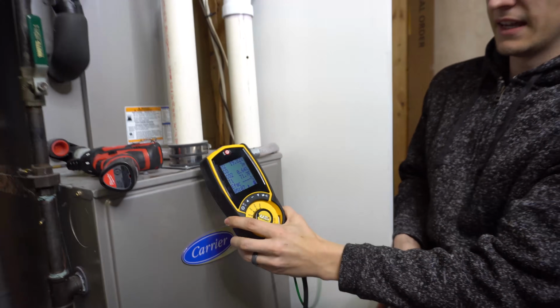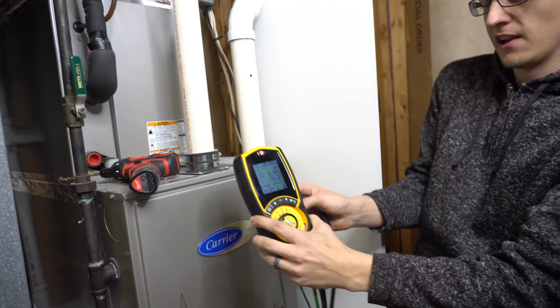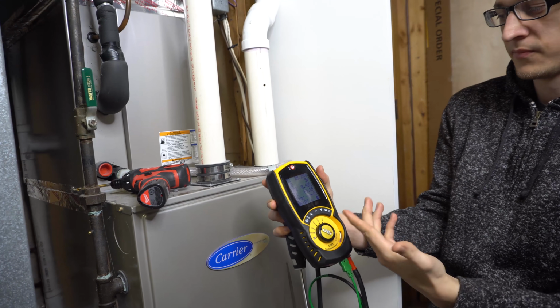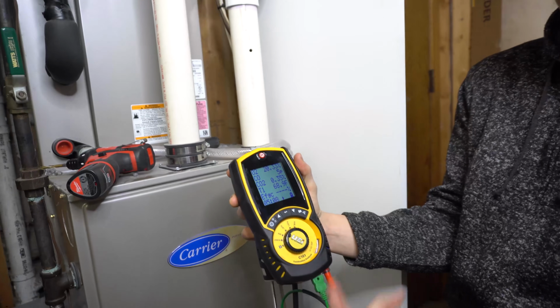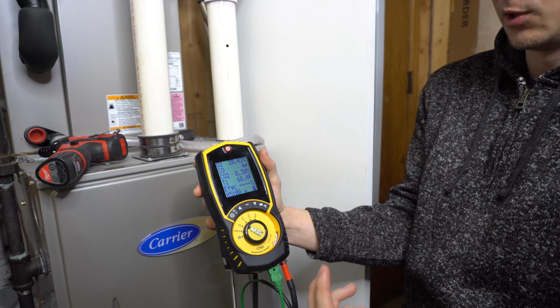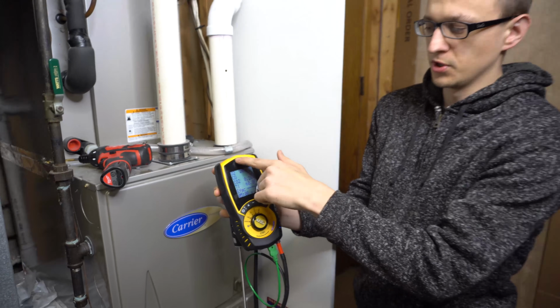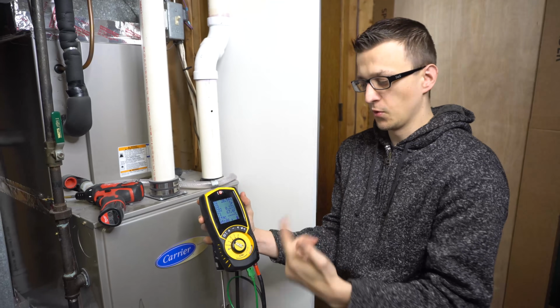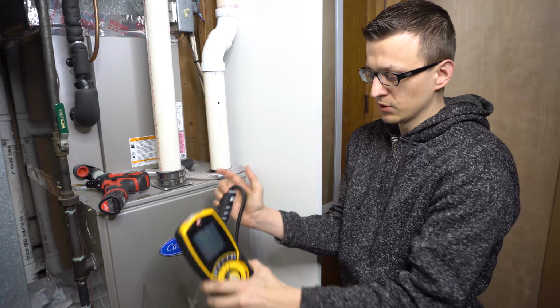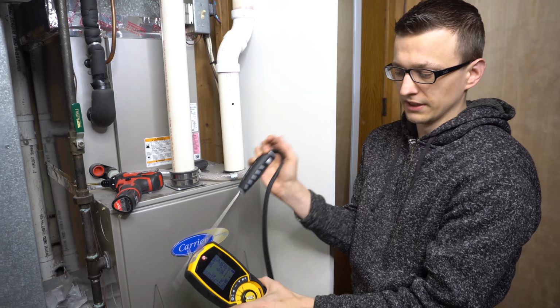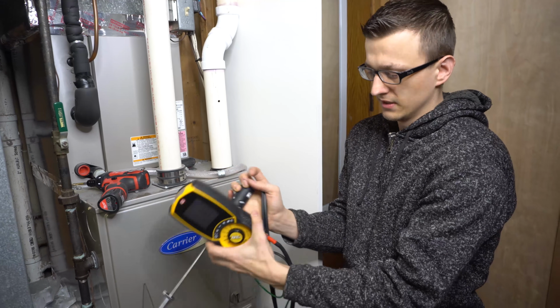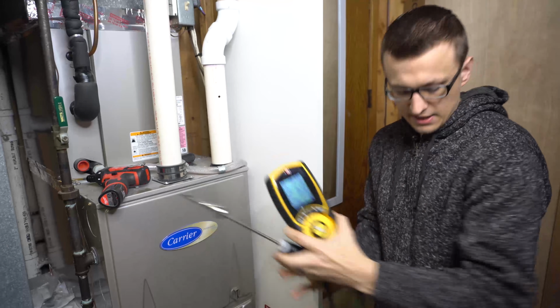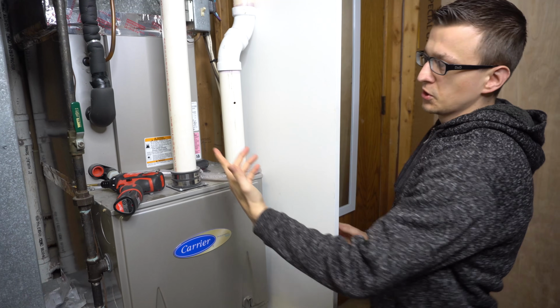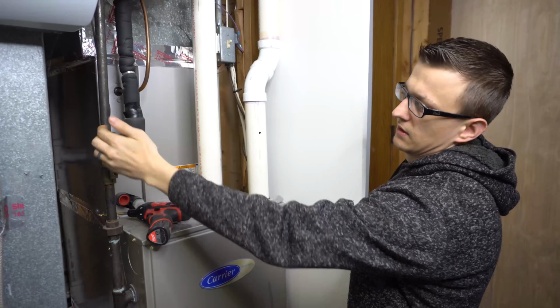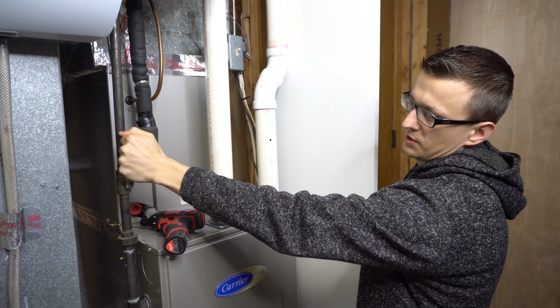So take this out, and typically I like to let my analyzer cool off completely, or zero out, before I turn it off. It does have a little purge cycle when you turn it off. It gives it 10 seconds before it completely turns off. But I like to let it actually purge out completely before I power it off. So I just leave my analyzer on, and then to turn off my furnace, I like to just turn off the gas to the furnace first.